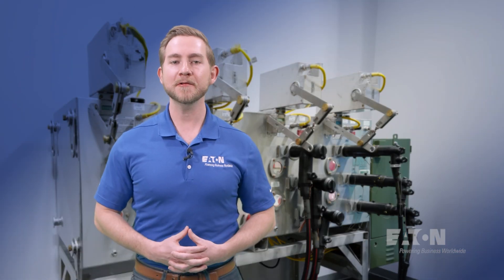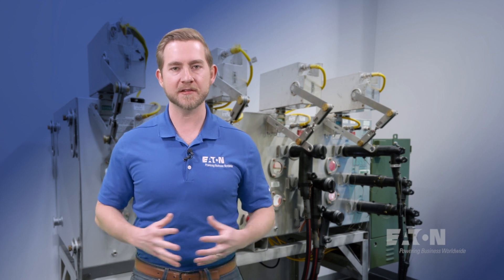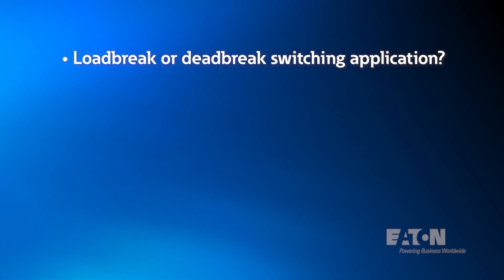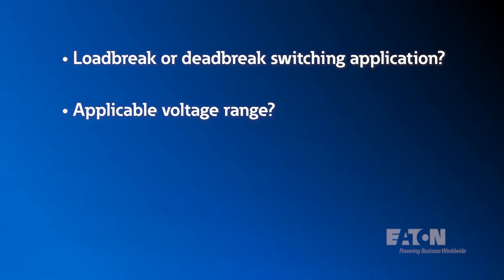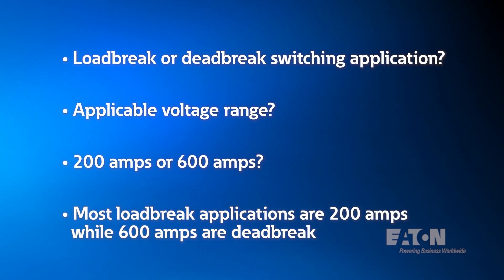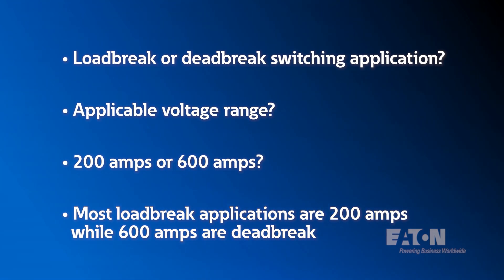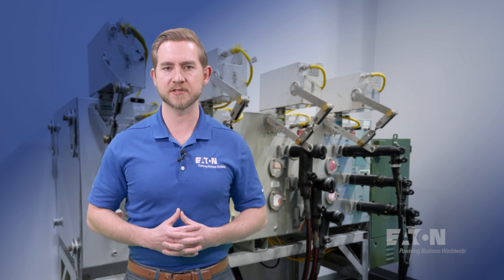So, how do we know which connector to choose? Selecting the right connector is dictated by a few key things. First, we need to know if this is a loadbreak or a deadbreak switching application, the applicable voltage range, and if the application is 200 amps or 600 amps. Remember that most loadbreak applications will fall into the 200 amp rated category, while 600 amp applications will be deadbreak. To achieve a 900 amp deadbreak rated application, additional equipment considerations must be taken.